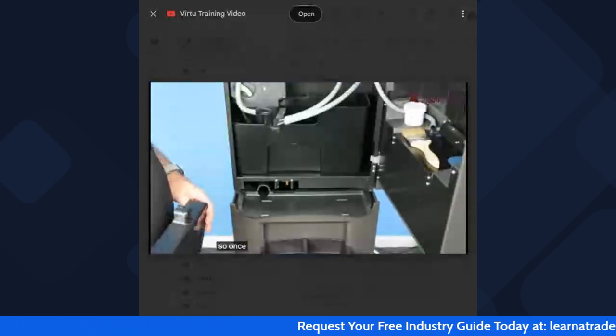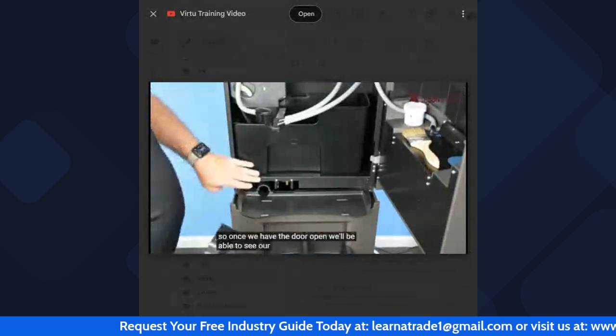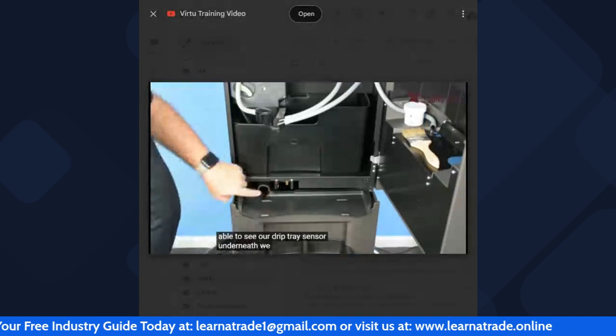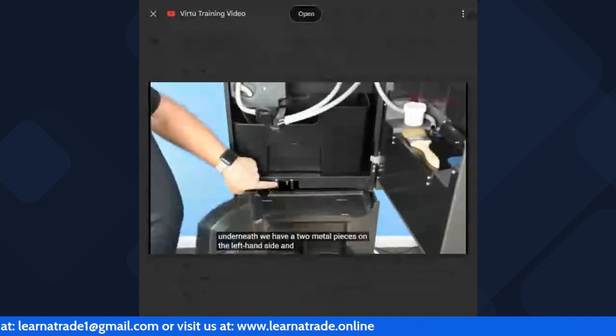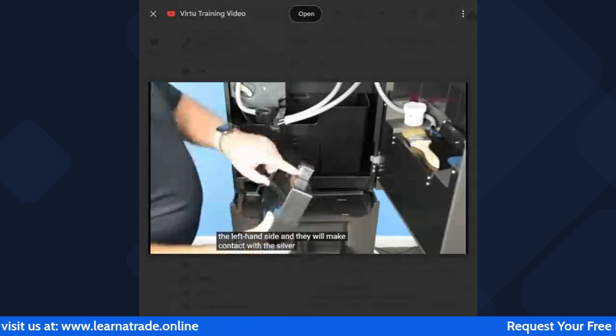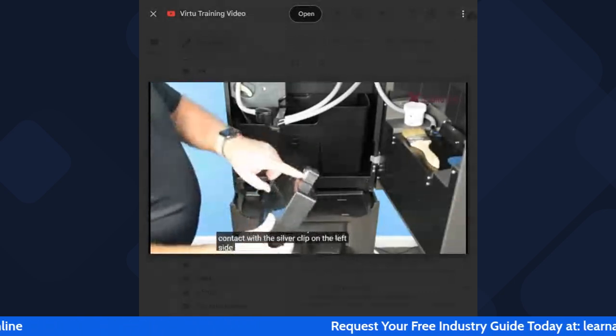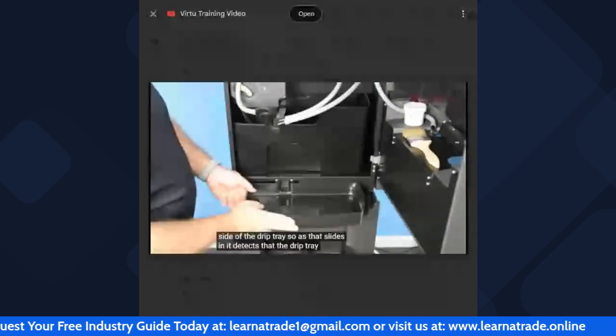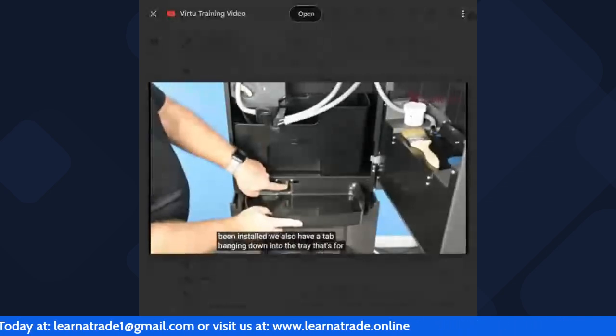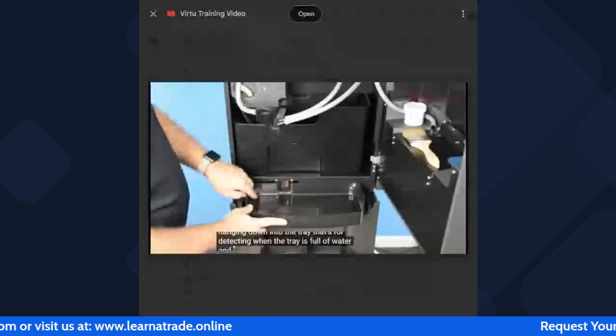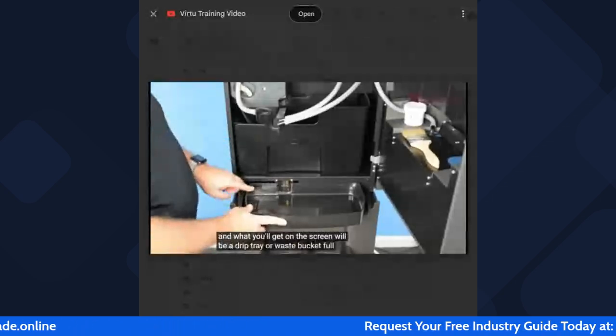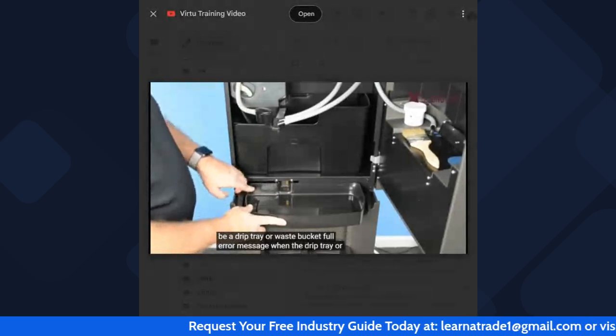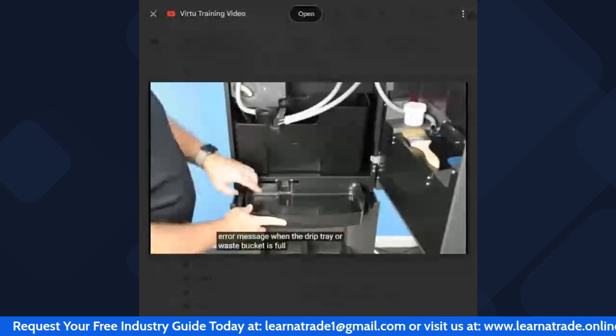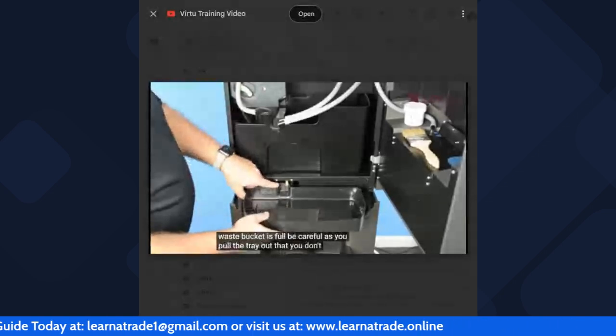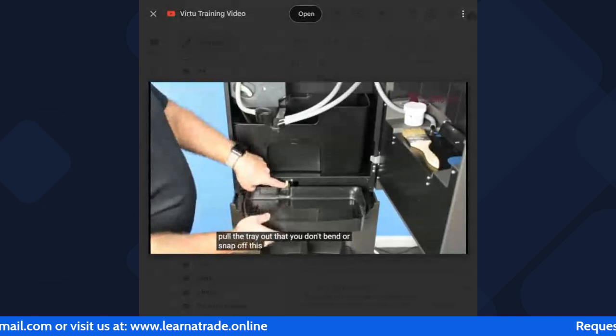So once we have the door open, we'll be able to see our drip tray sensor underneath. We have 2 metal pieces on the left-hand side, and they will make contact with the silver clip on the left side of the drip tray. Tab hanging down into the tray, that's for detecting when the tray is full of water. And what you'll get on the screen will be a drip tray or waste bucket full error message when the drip tray or waste bucket is full. Be careful as you pull the tray out that you don't bend or snap off this water sensor.